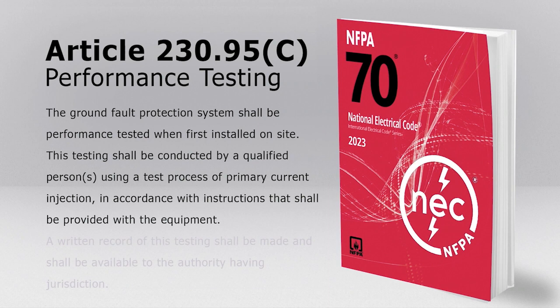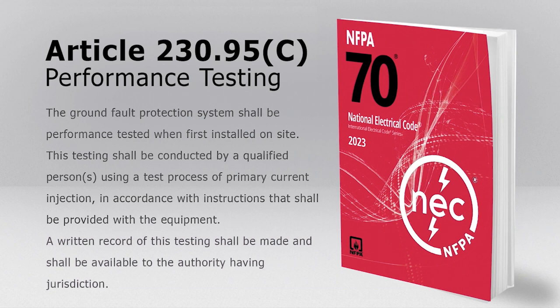So 230.95(C) says this: the ground fault protection system shall be performance tested when first installed on site. This testing shall be conducted by qualified persons using a test process of primary current injection in accordance with the instructions that shall be provided with the equipment. A written record of this testing shall be made and shall be available to the authority having jurisdiction.